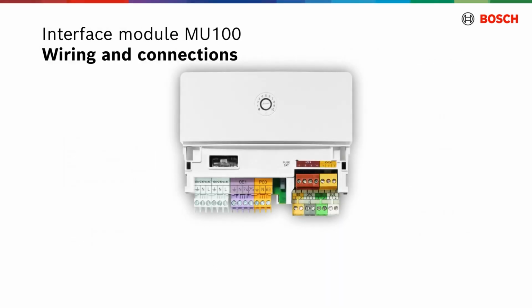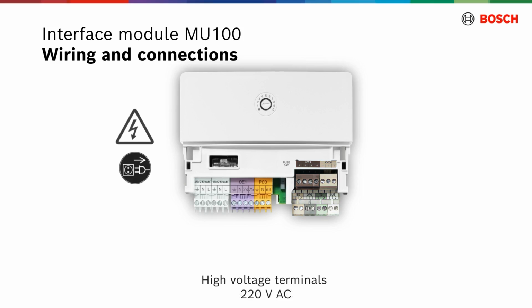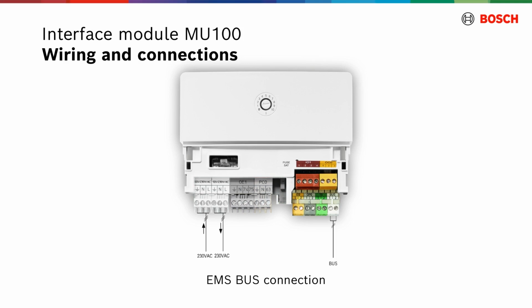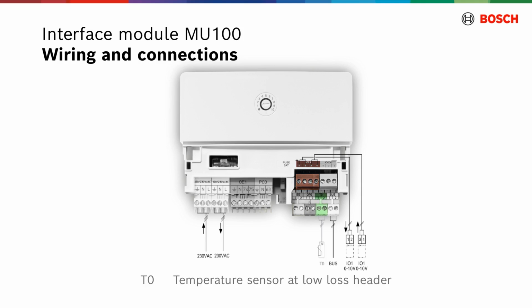Interface module MU100 has low voltage terminals for the temperature sensors and fault and control outputs, and the high voltage terminals for the power supply of the function modules. On the right low side, there is a terminal for EMS bus connection. When the heating system is controlled by BMS with the terminals IO1 on the low side, module MU100 sends input and output signals from BMS to the heat source. With the temperature sensor T0, module MU100 records the temperature at a low-loss header.